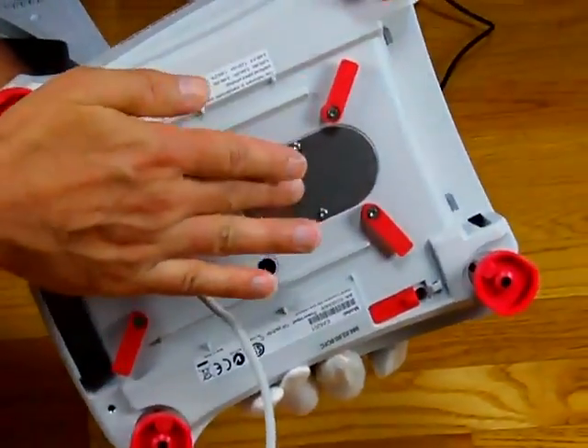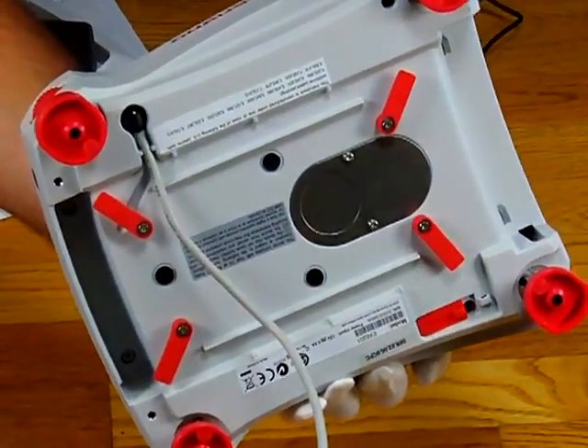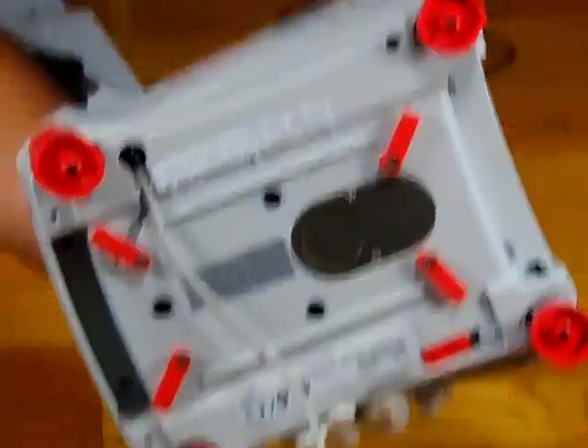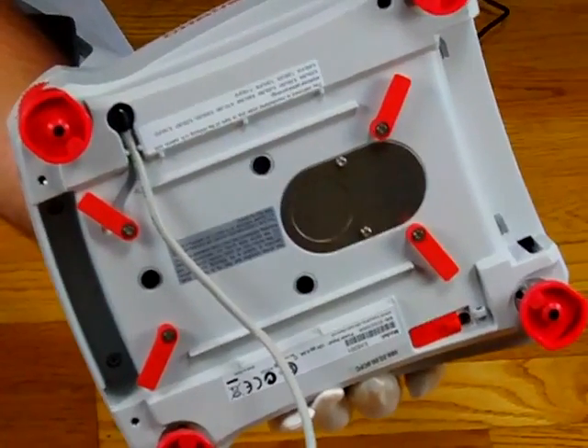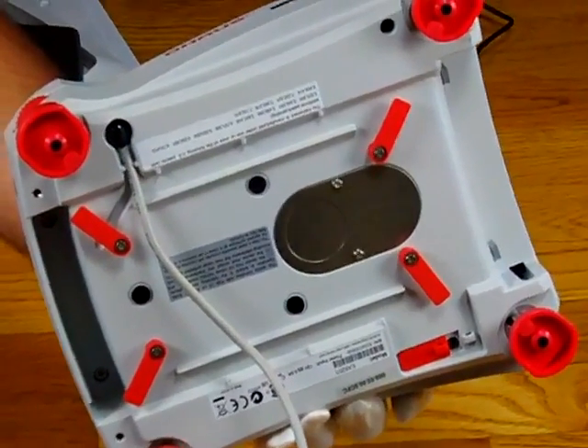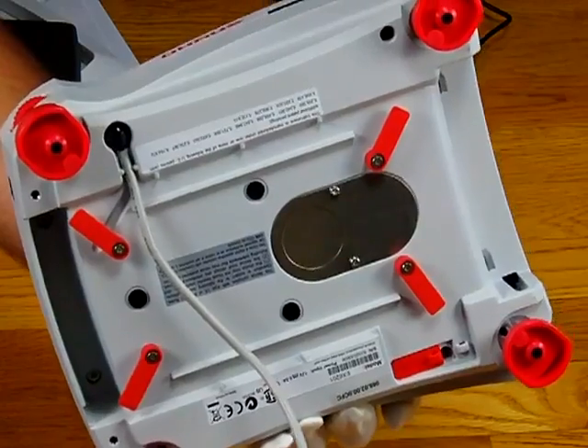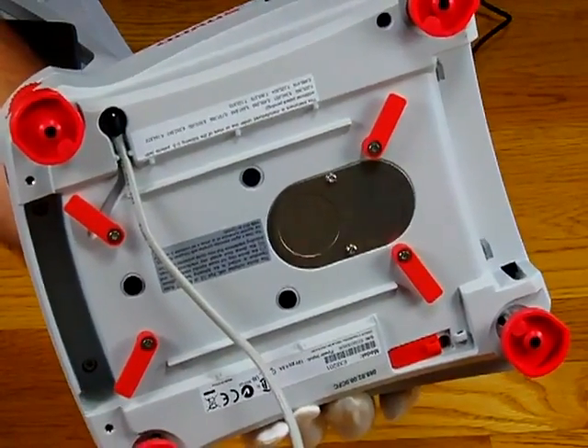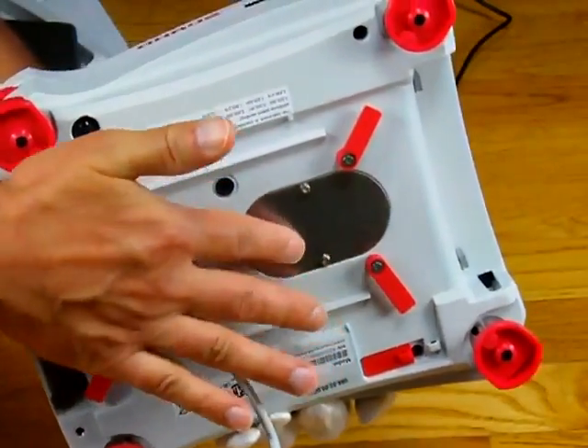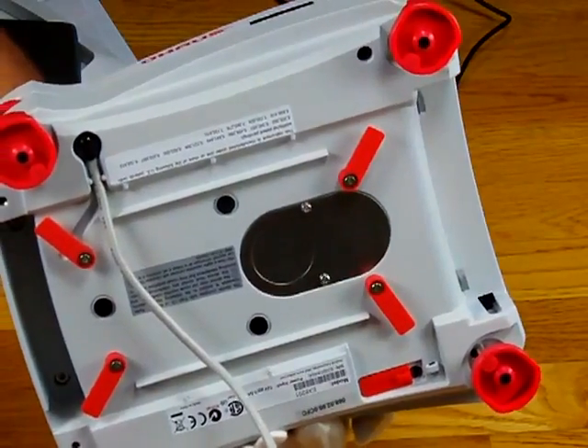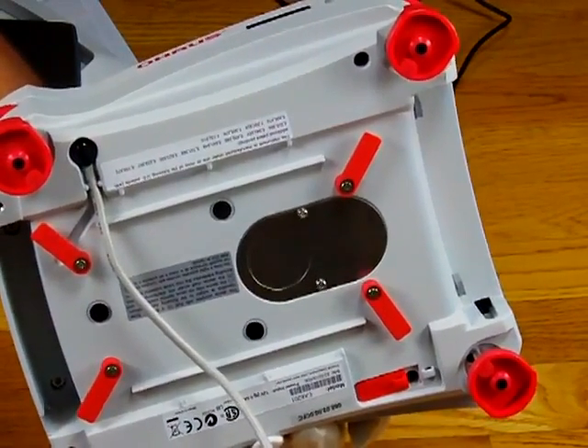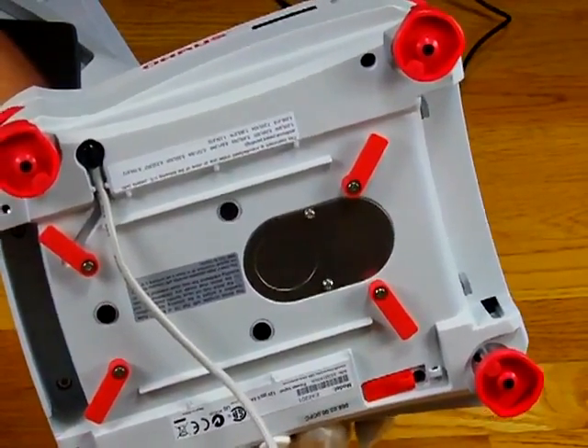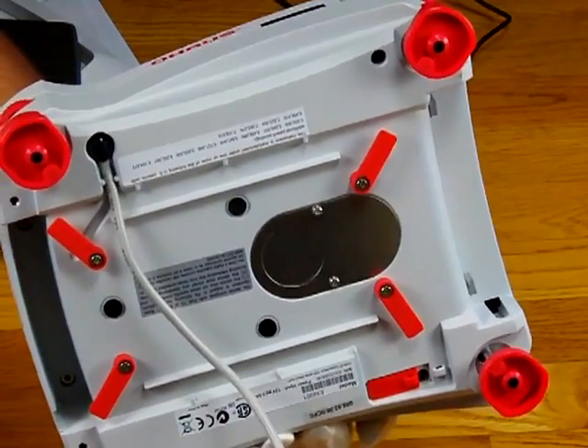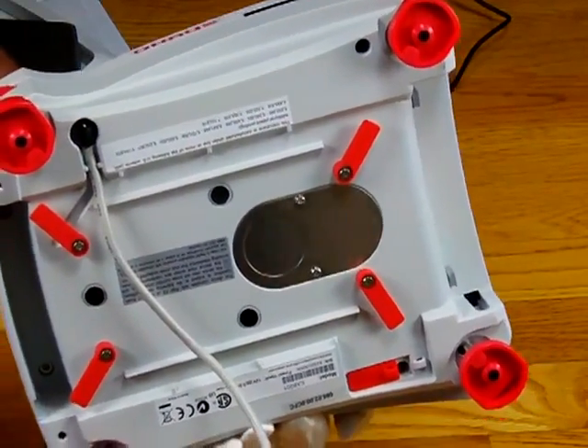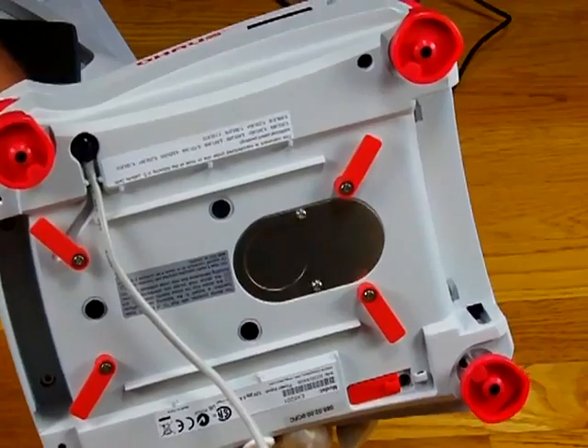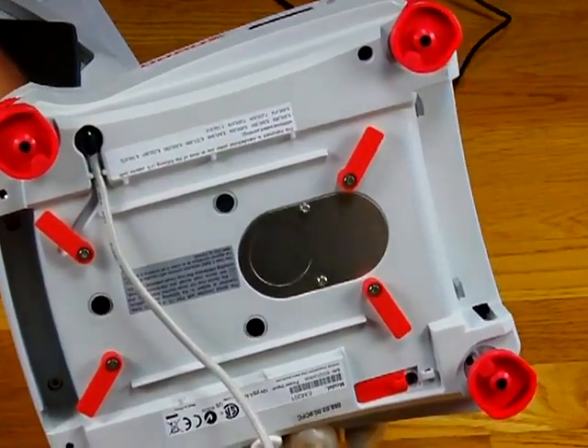We also have this port here for the weigh-below function. If you're doing something like specific gravity, or weighing a hot item, since heat affects the balance, you wouldn't want to place it on top. Instead, you'd hang it below. You open up this port, there's a little hook, you hang a wire, and do your weighing beneath the balance. It's also useful for a very large item, so it doesn't overhang the platform, and you can perform your weighing application that way.